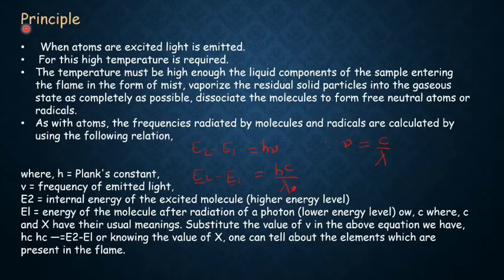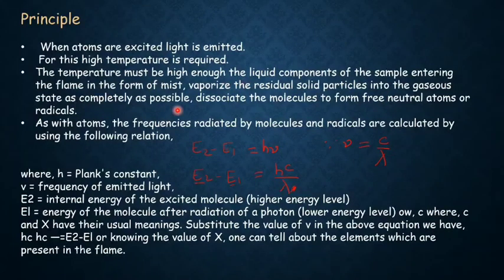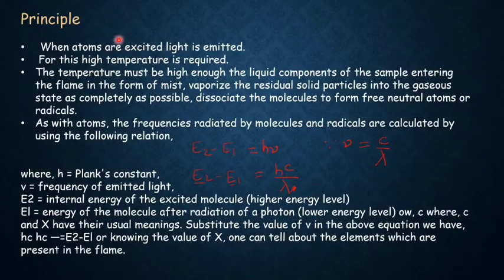The principle: the sample solution is aspirated into the flame, then it gets evaporated and atomized. When the atoms are excited, light is emitted; for this excitation, high temperature is required. The liquid components of the sample entering the flame in the form of mist vaporize the residual solid particles into the gaseous state as completely as possible, and after that dissociate the molecules to form free neutral atoms or radicals. The temperature must be high for vaporization and dissociation to take place.